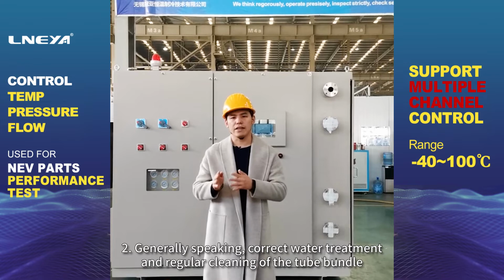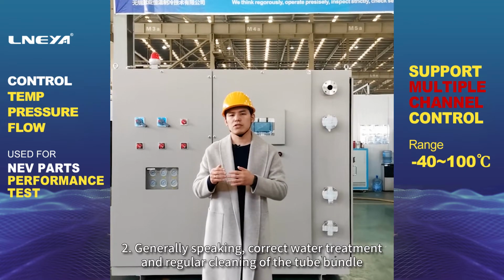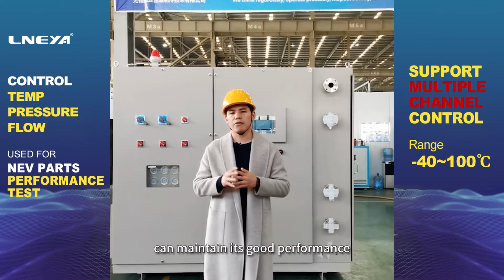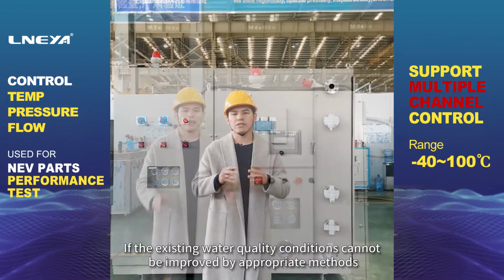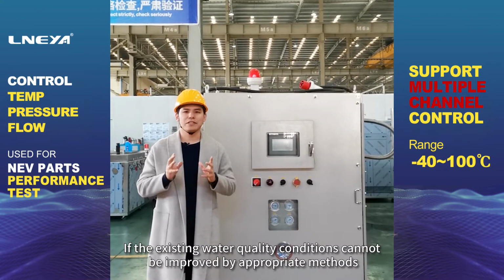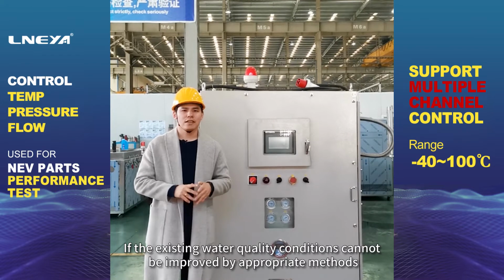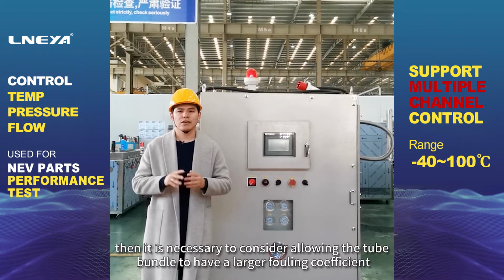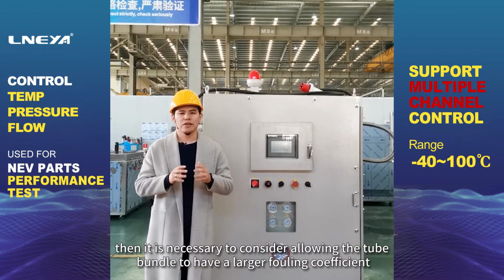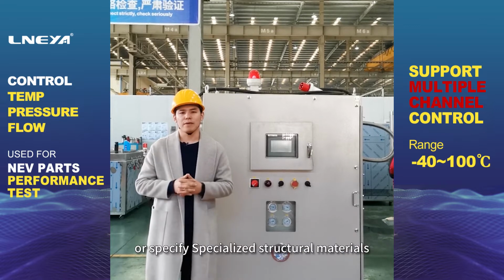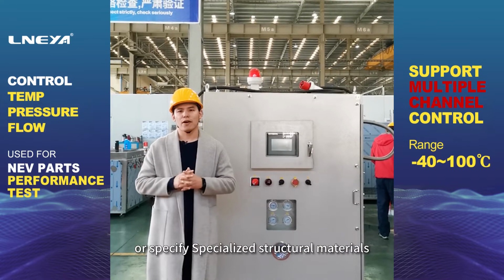Second, generally speaking, correct water treatment and regular cleaning of the tube bundle can maintain its good performance. If the existing water quality conditions cannot be improved by appropriate methods, then it is necessary to consider allowing the tube bundle to have a larger fouling coefficient or specify specialized structural materials.